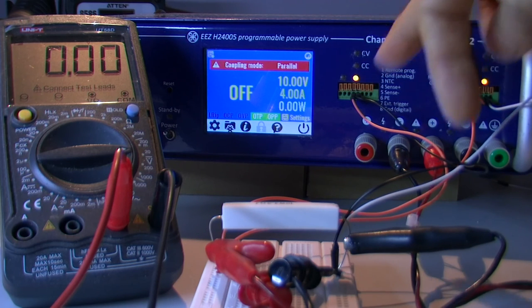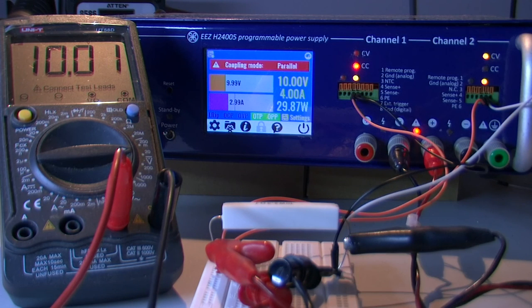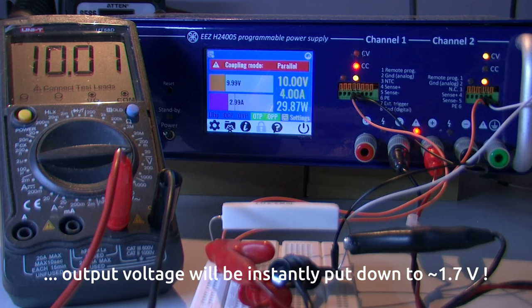When connecting remote sensing input to outputs you need to take care about polarity. And we added reverse polarity detection. If you mistakenly swap those cables, that will be detected and firmware will automatically switch off power output.